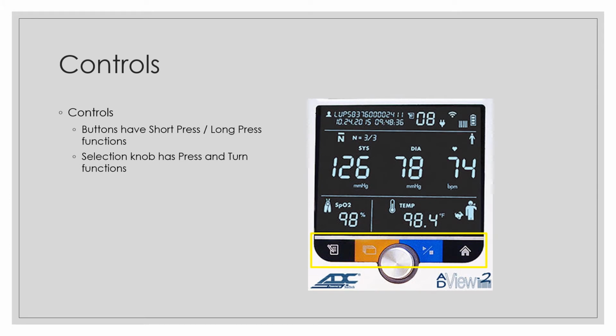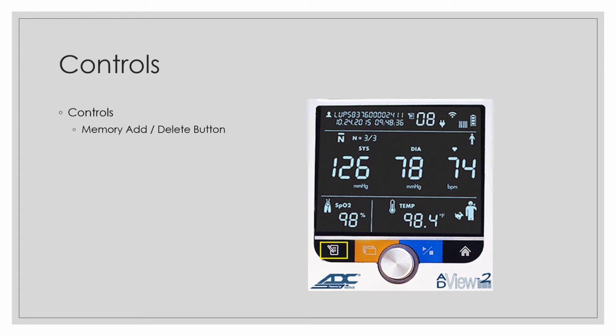There are 4 pressure-sensitive buttons and a selection control knob at the bottom of the unit. The buttons have single short press functions, and 2 of the buttons, the memory and mode buttons, have long press functions as well. The selection control knob has a turn selection function and a press function. The first button with the notepad icon is the memory add button. To the right of the memory button is the toggle mode. This button is used to change between adult and pediatric mode.